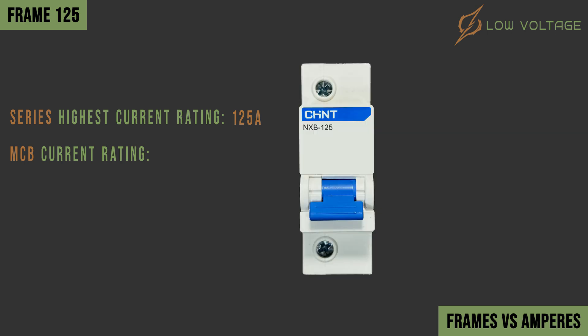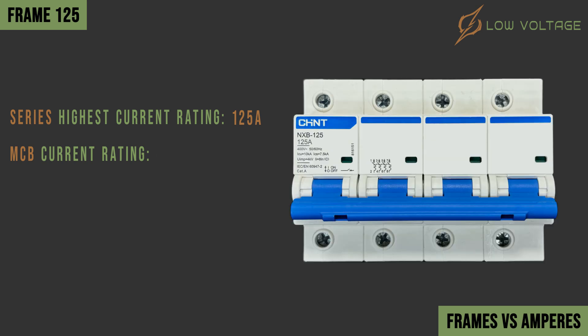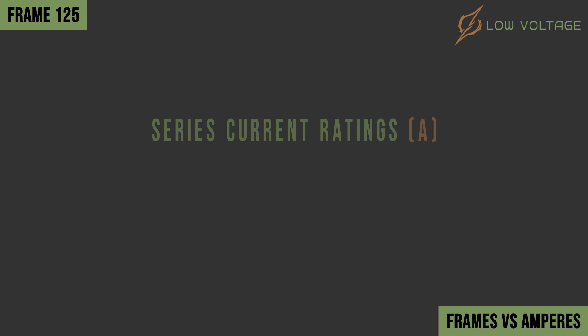Another example of a breaker within the same 125 amperes frame, but with a different rating: this MCB has a current rating of 63 amperes. The last example is also a breaker within the same frame, having a current rating of 125 amperes. Frame 125 can have current ratings between 10 amperes reaching a maximum rating of 125 amperes, and these ratings can vary between manufacturers.